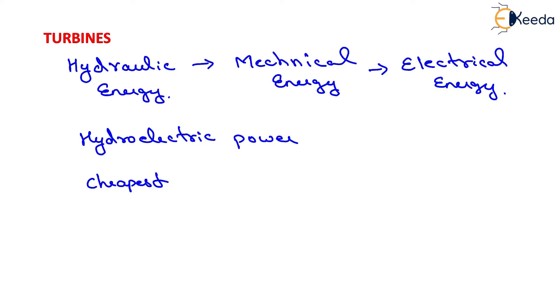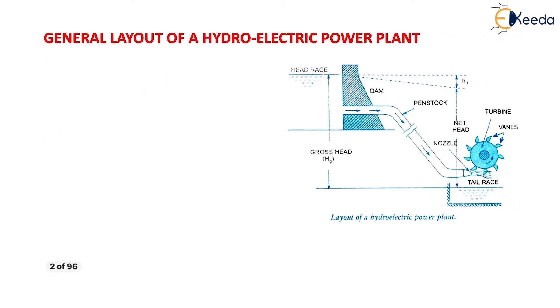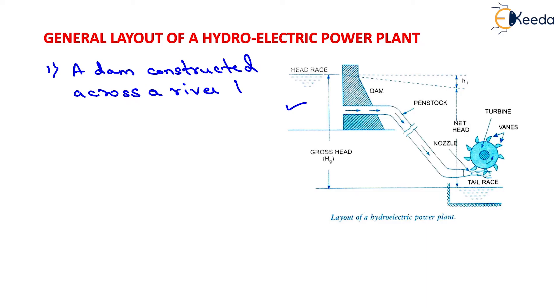We will discuss the general layout of a hydroelectric power plant. This figure shows a general layout which consists of a dam constructed across a river to store water. Second, pipes of large diameter called penstocks, which carry water under pressure from the storage reservoir to the turbine. These pipes are made of steel or reinforced concrete.